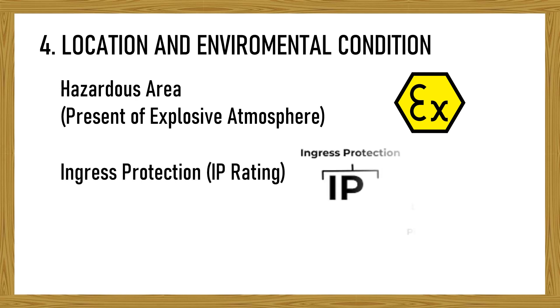Ingress protection of instrument enclosure must also be specified to suit the environment, whether it is located in rain or dry, dusted, offshore installation, and etc. The ambient temperature must also be considered because it will affect some parts such as electronic parts and elastic material such as seal and packing.